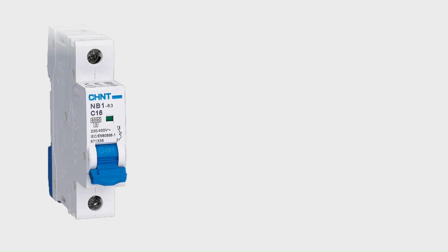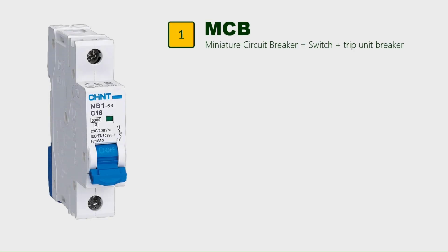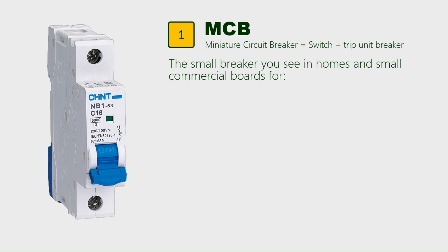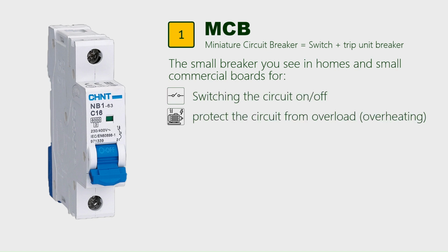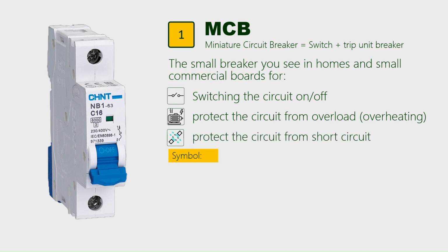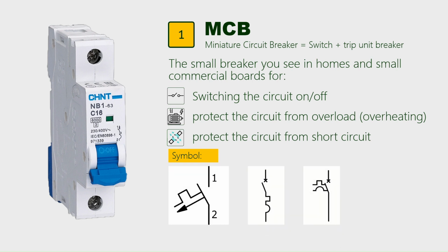The MCB, or miniature circuit breaker, is the switch plus trip unit breaker you see in homes and small commercial boards. Its job is switching the circuit on and off, protecting the circuit from overloads and overheating, and protecting the circuit from short circuit. It usually works at 230 or 400 volts and it's perfect for lighting and socket circuits. These are MCB symbols you might see on electrical schematic drawings.